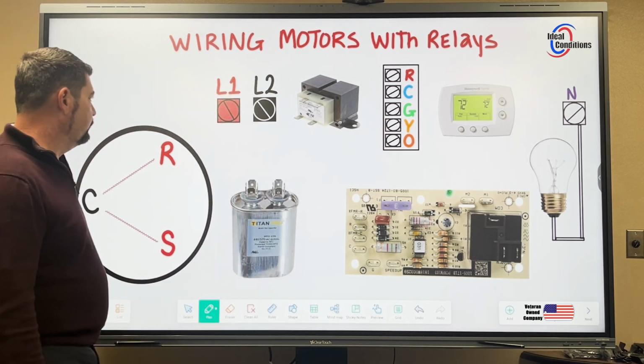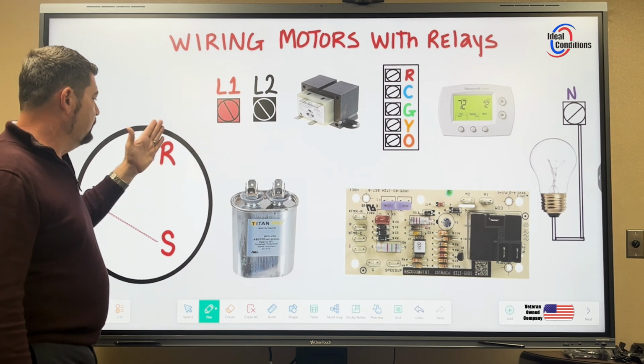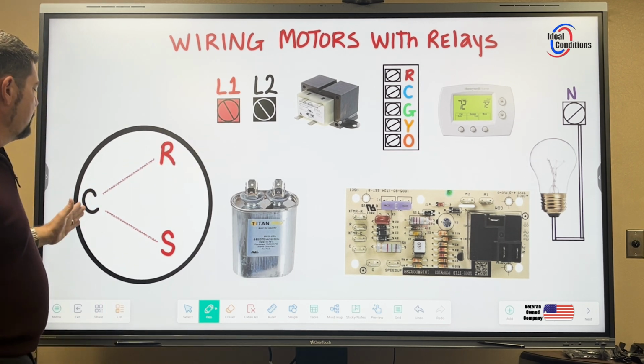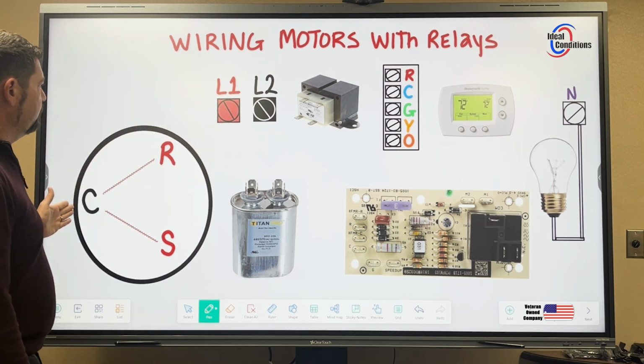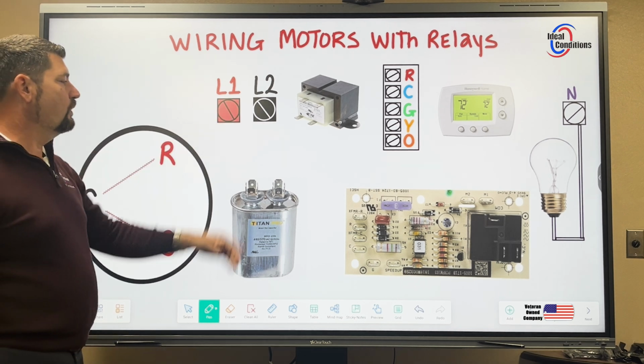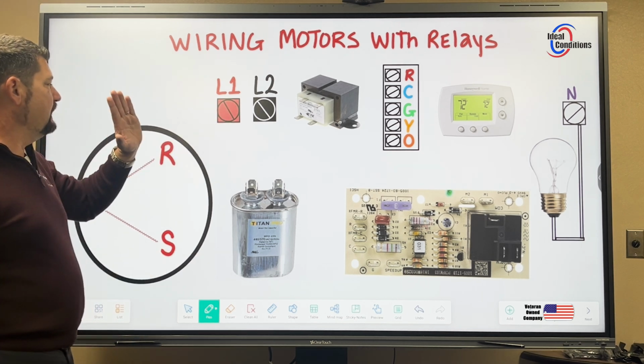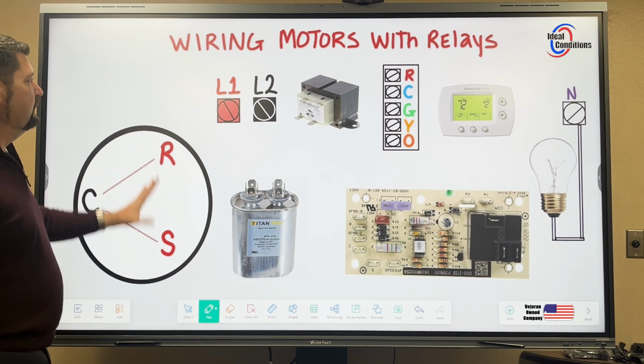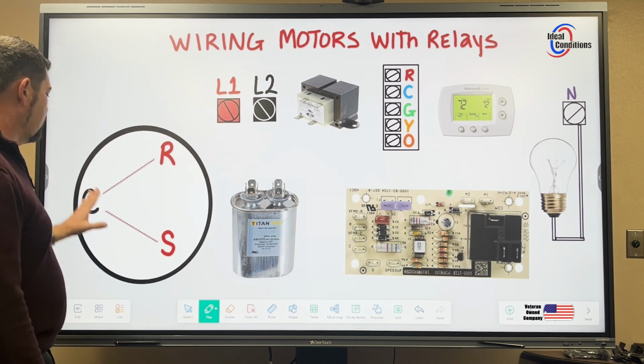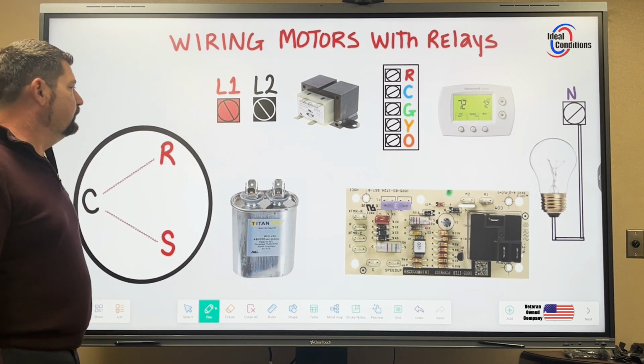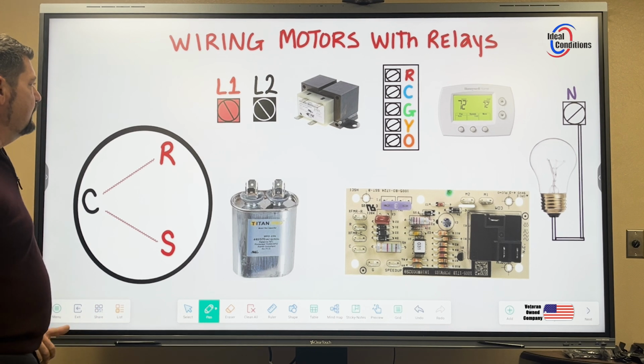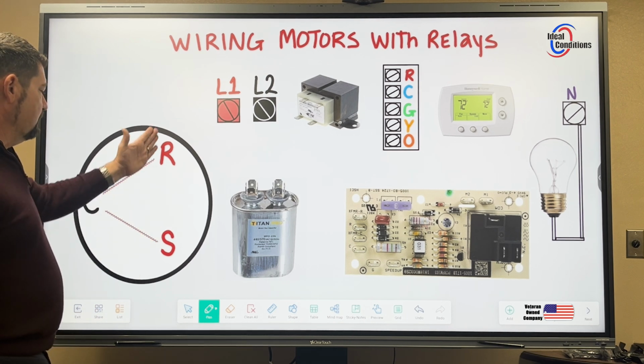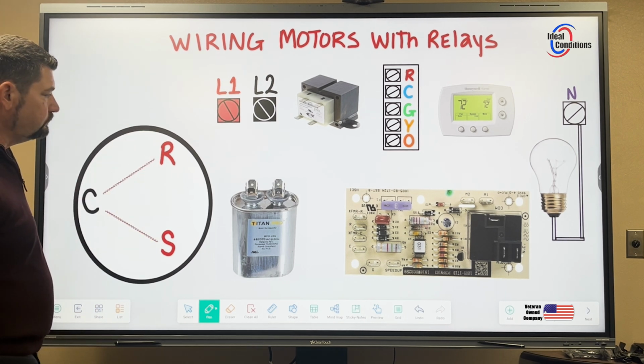We have a run capacitor. We have both legs. As you can see, I've color coded the motor with red terminals and black terminals, as well as your L1 and L2. That does not mean that run and start windings have to be wired to L1 and your common winding has to be wired to L2. That's just to identify that run and start need to be on the same leg. Okay.